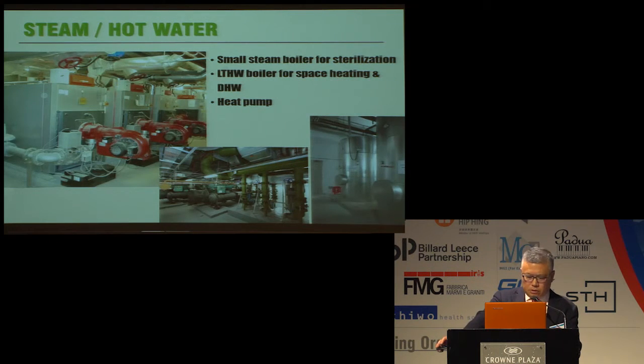In the past, hospitals used steam to provide domestic hot water and hot water for space heating. Now this is very costly because energy conversion is very inefficient. A more energy efficient way is to use a dedicated steam boiler for sterilization and then a high efficiency gas-fired water heater for domestic hot water. A water-to-water heat pump can also recover energy from the condenser water circuit rejected from the central chiller plant to generate low-grade hot water for space heating and also terminal reheat for humidity control.